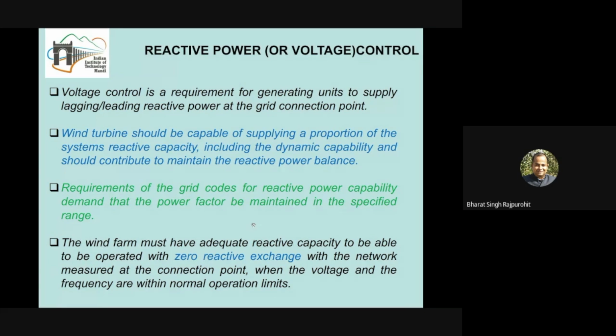Here the philosophy for the reactive power control, what is expected from the renewable energy sources, is that they should be able to operate with zero reactive exchange with the grid. What is the meaning of that? Zero reactive exchange means that they are neither taking reactive power nor giving reactive power to the grid. But in a broader sense, the net reactive power exchange should be limited. If required, reactive power should be supplied to the grid to maintain the voltage profile, and if there is excess reactive power, the wind farm or solar farm should also be able to absorb reactive power to maintain the voltage profile. So this is expected, which means both ways are possible.